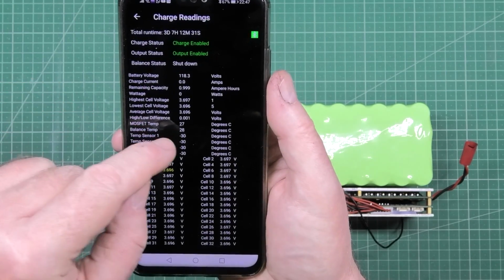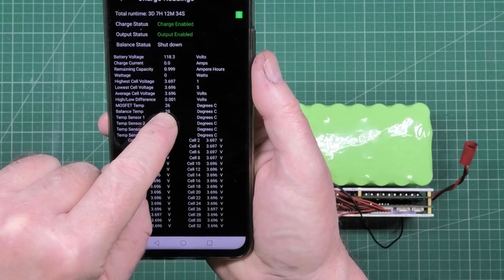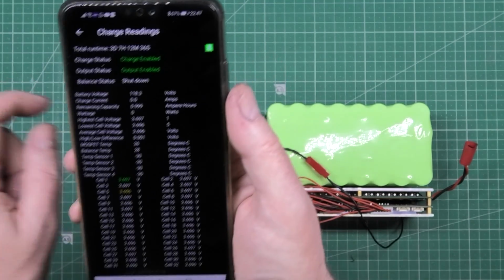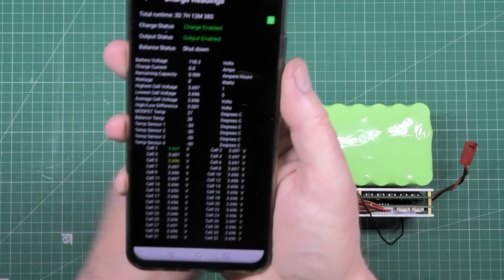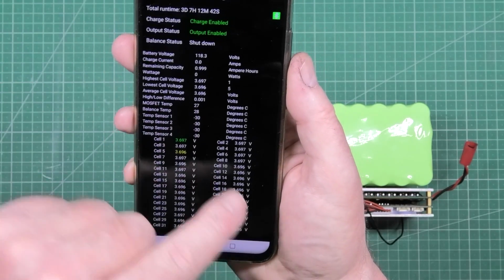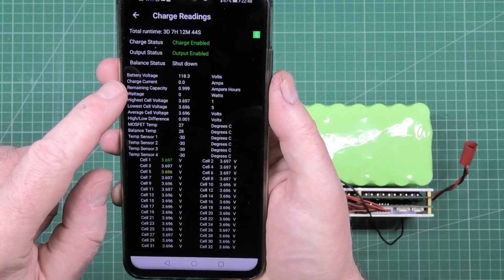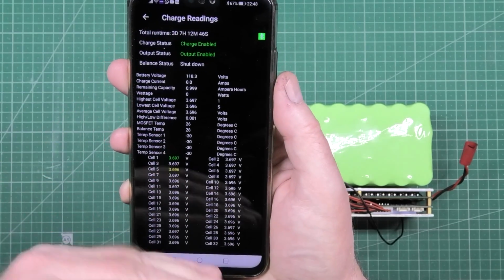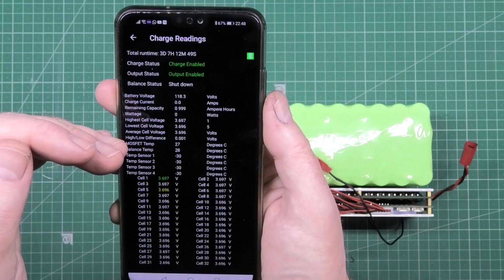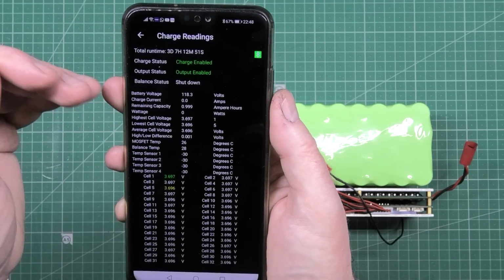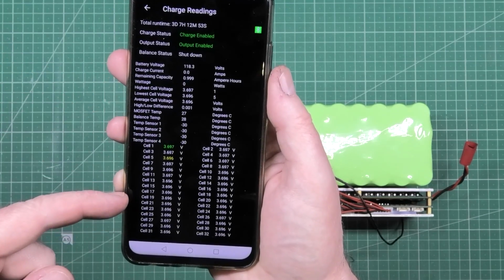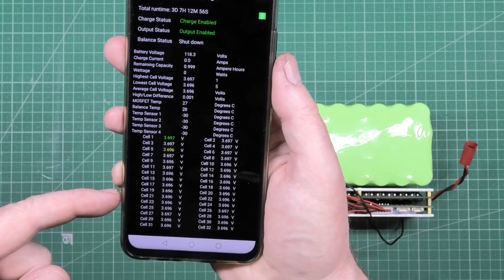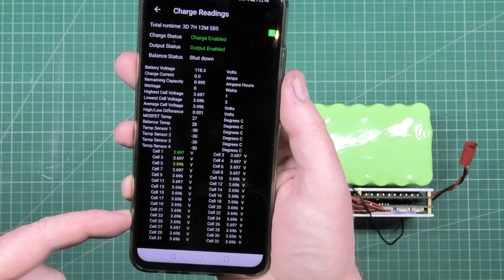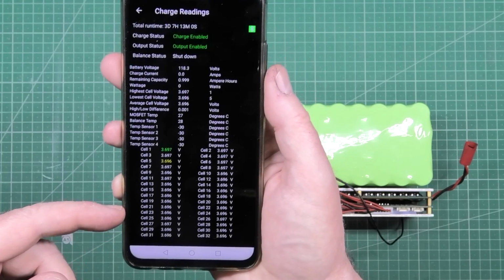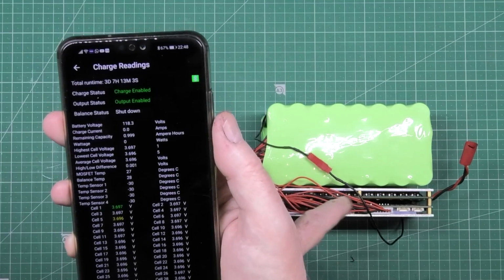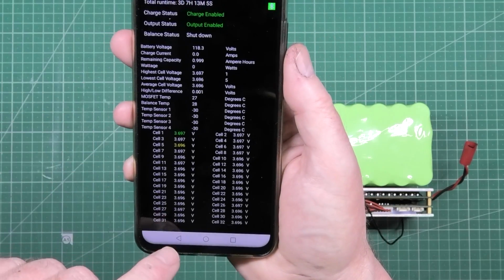Your balance temperature, which is at 28 at the minute, is something to keep an eye on when it's charging and balancing. If that goes above 60 degrees it'll stop balancing until it comes down to about 58 degrees, then it'll start balancing again. If it gets too high, you need to change the maximum balance resistance, drop it down a bit so it doesn't get too hot, that's all.